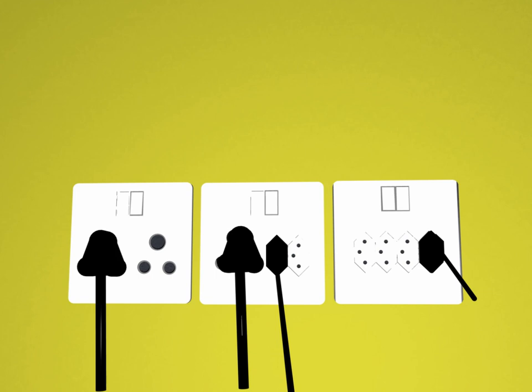Like Schuko and Europlug, the line and neutral pins are 19mm long and on centers spaced at 19mm. The pins have a diameter of 4.5mm, intermediate between Schuko and Europlug. In common with the Europlug there is an insulating sleeve around the base of the line and neutral pins.